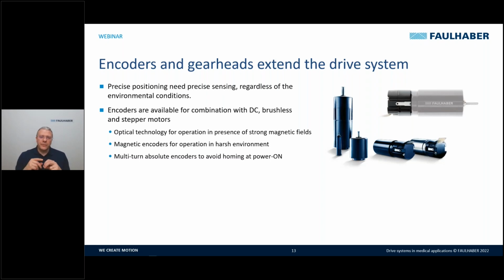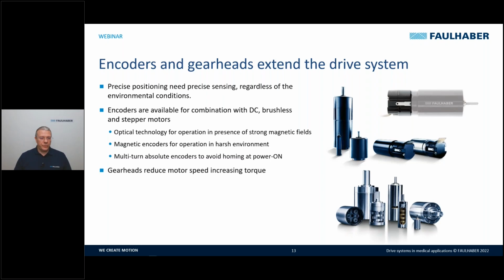Then we have a multi-turn absolute encoder, which is another interesting product, because it gives us the possibility to memorize the position in the application even in presence of a power off. We have one wire connected to an external backup battery, and this conserves the memory position in the application. So at the next power on, there is no need for a homing operation in order to get the real position in the application.